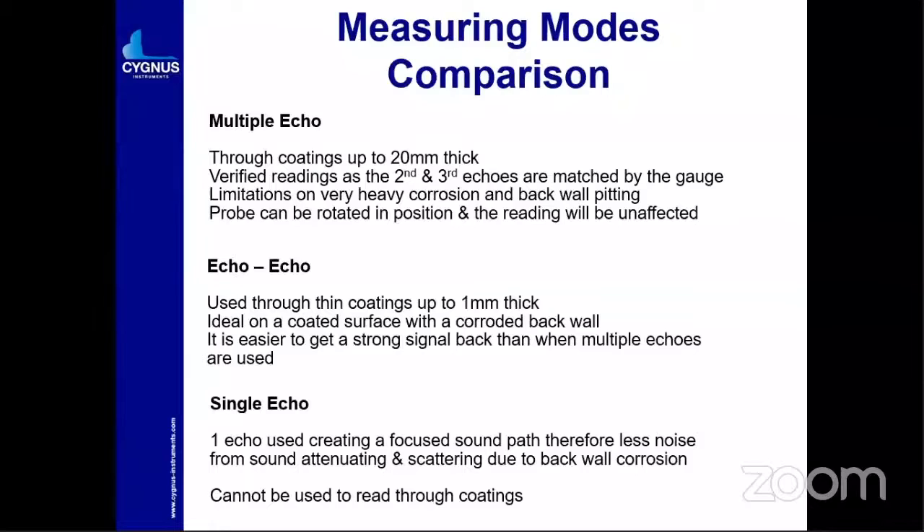Echo-to-echo is used through thin coating up to 1 mm with a TR probe. Single echo mode creates focused sound and produces less noise. Single echo is used especially in A-scan and B-scan applications. For multiple echo mode — through coating up to 20 mm — verified readings from the second and third echoes are matched by the gauge. It has limitations where there is heavy corrosion and back-wall pitting.